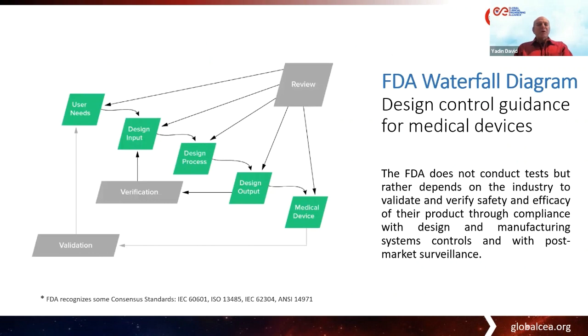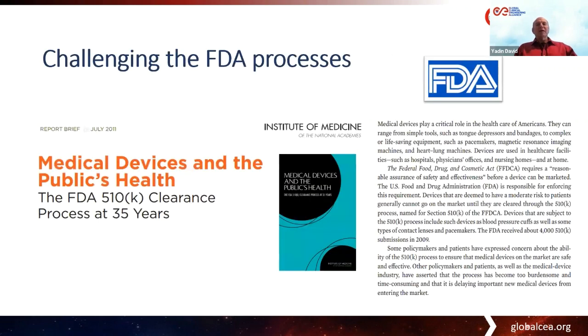There's the famous waterfall process of how a device should be designed and how we, the manufacturers, must control the process, knowing the risk and finding out how well it's controlled, and if it's not mitigated completely, did we communicate that to the user through the instructions for use?